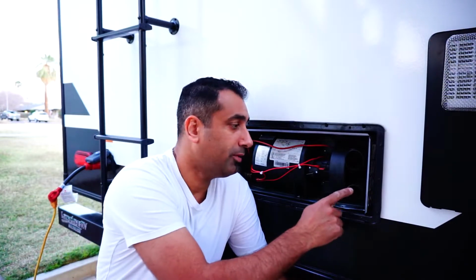There are multiple reasons for a furnace to short cycle. If we're not pushing enough air from the furnace inside the trailer, then there is a heat buildup that trips the high limit switch. The second one could be a blocked exhaust vent. So if you check these two first, you could save yourself a lot of headache.